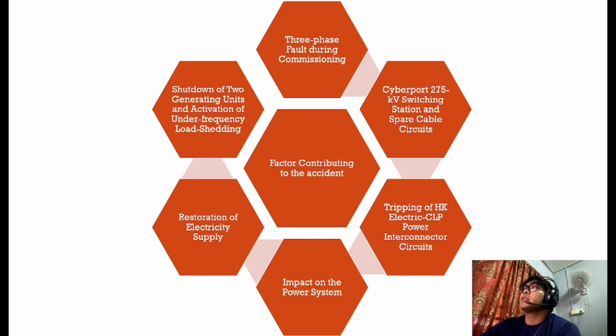So these are the factors contributing to the accident. First is the three-phase fault during commissioning. Next is the Cyberport 275 kV switching station and spare cable circuit. The third one is the tripping of the HK electric CLP power interconnecting circuit. Fourth is the impact on the power system. The fifth one is restoration of electricity supply, and the last one is the shutdown of 2 generation units and activation of under frequency load shedding.